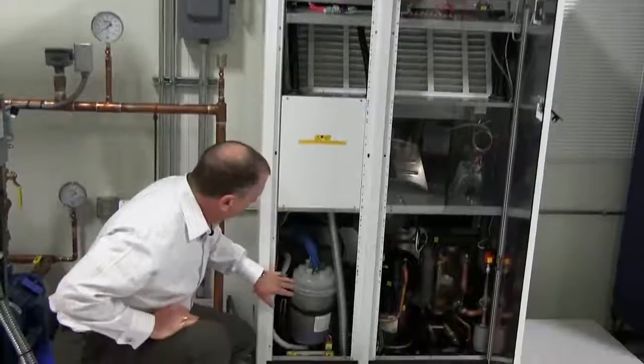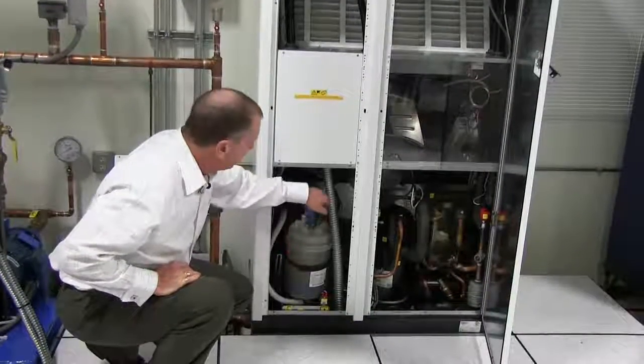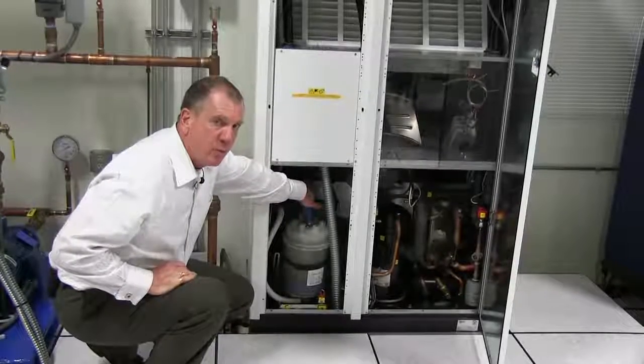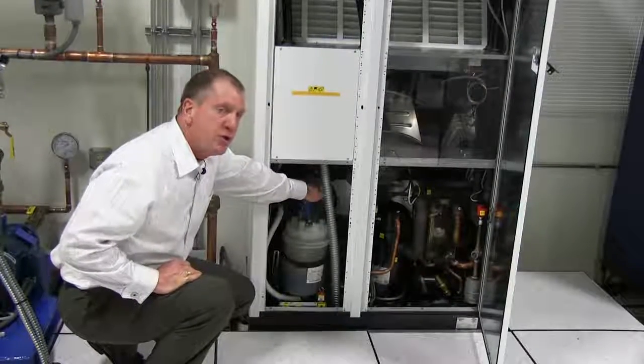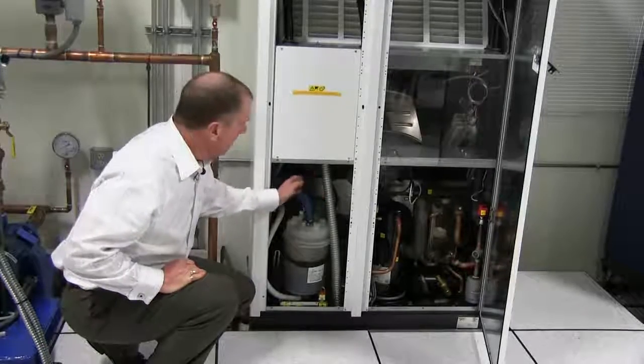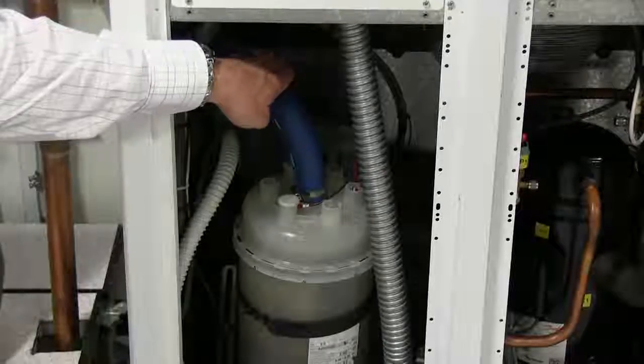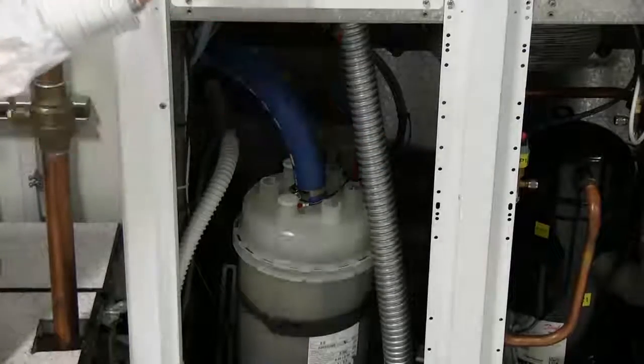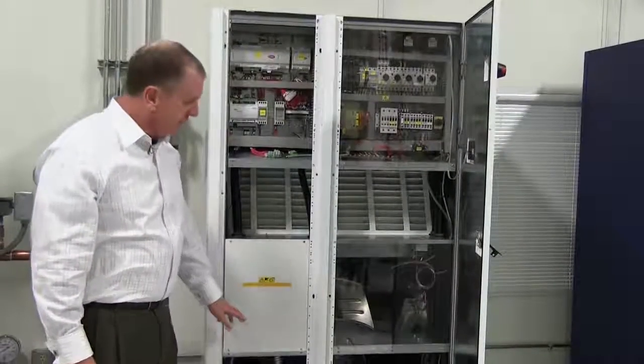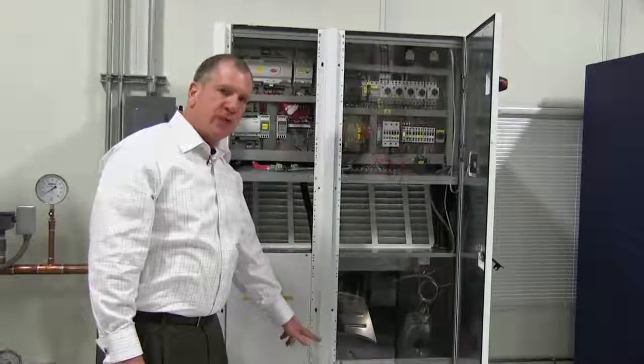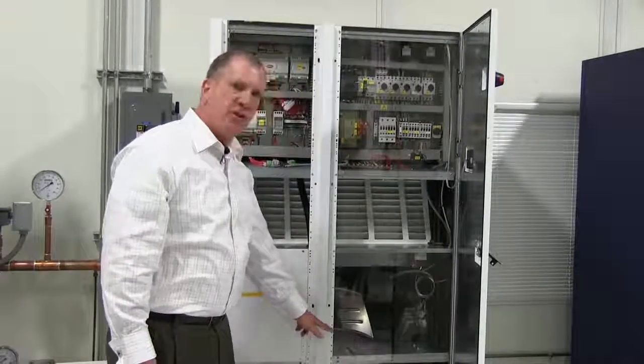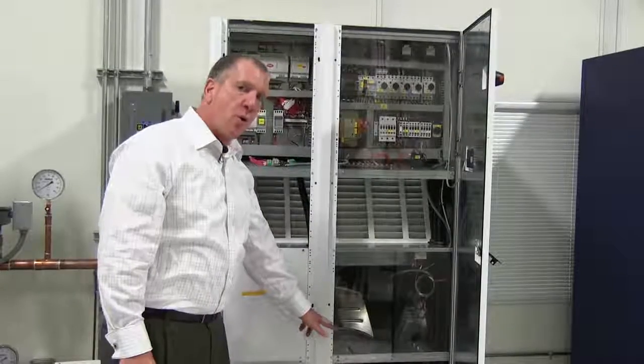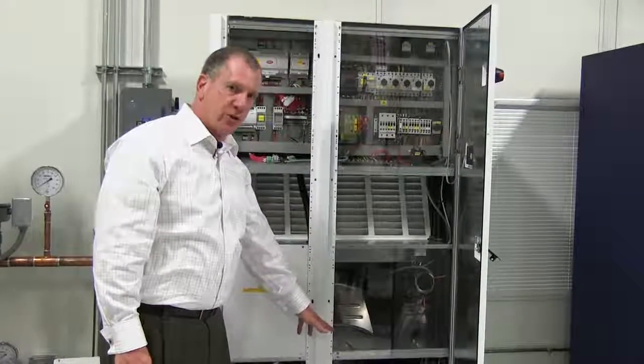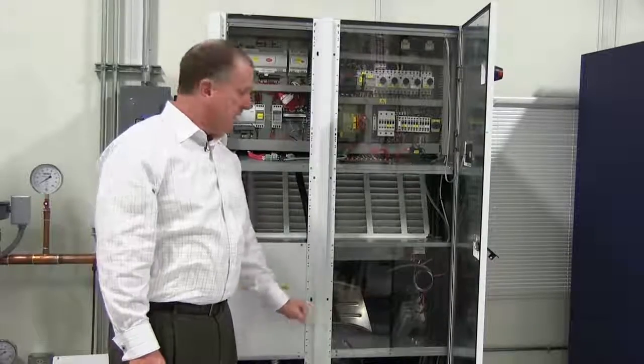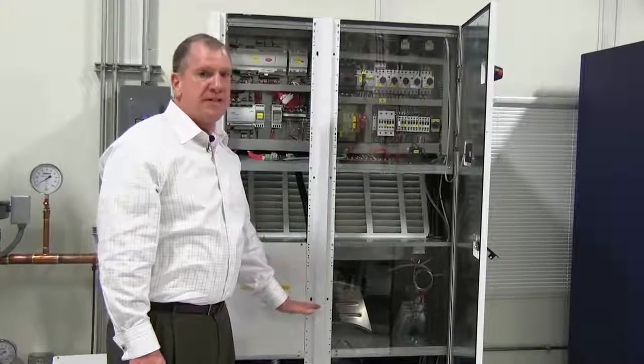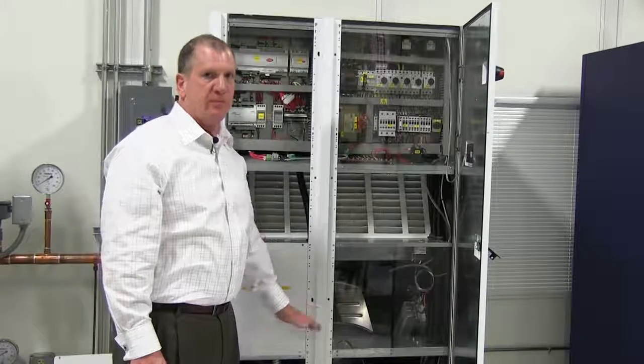On this side of the compartment, behind the steam canister humidifier, is our three-way valve. The three-way valve, when temperature is appropriate, would divert flow to the interlaced economizing coil above. There is always flow through the unit maintained through the condenser. On larger units with multiple compressors, we would have 2 compressors on a single circuit. Larger units still have 2 compressors on multiple circuits, or up to 4 compressors on 2 circuits. The 4 compressors allow staging of 25, 50, 75, and 100% capacity for the unit.